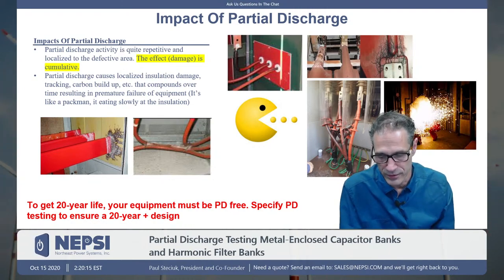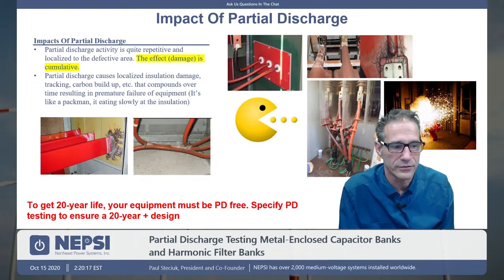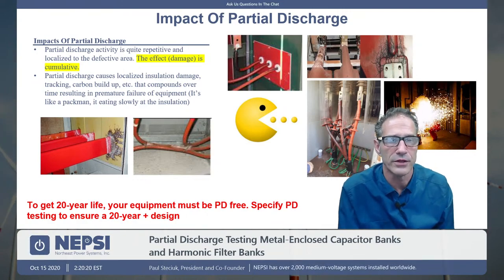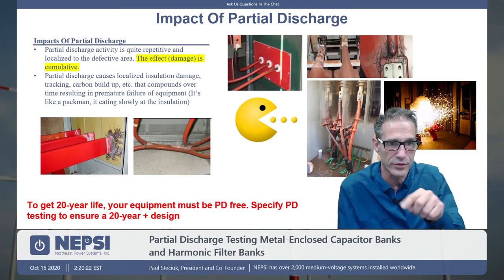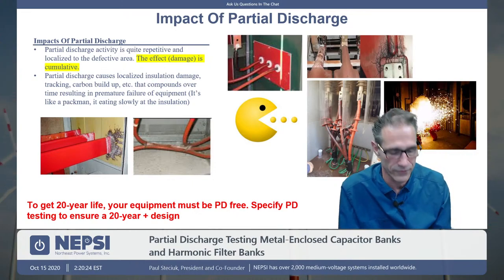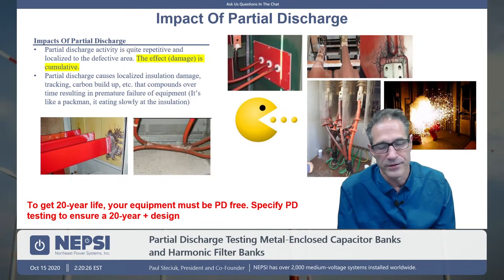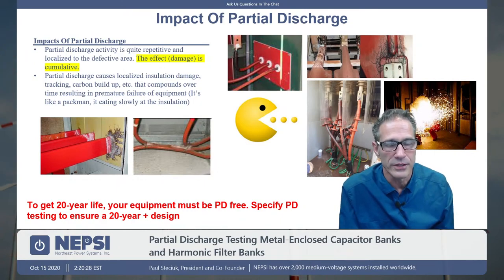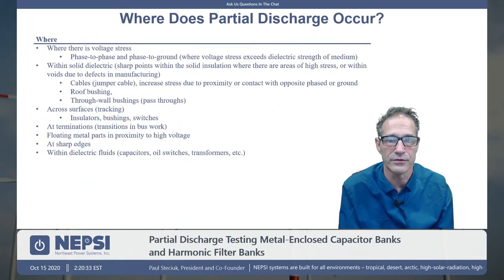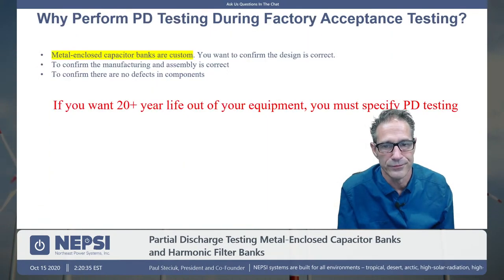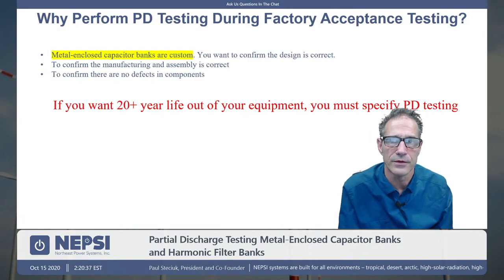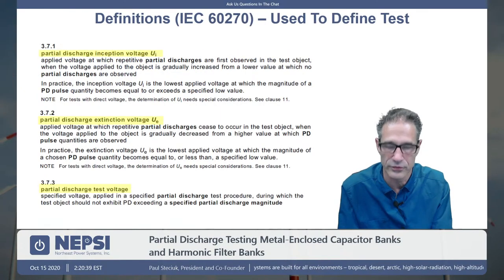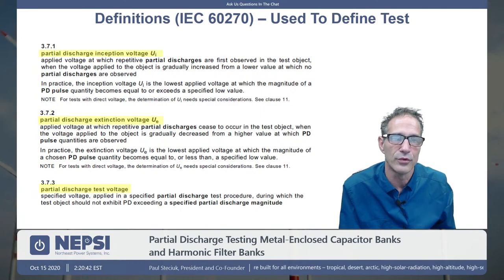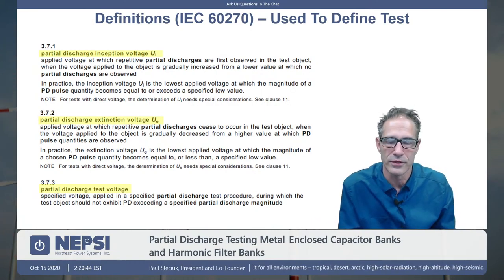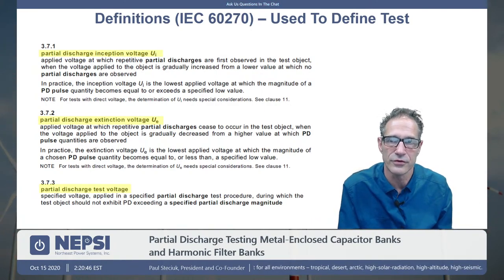I would suggest going to a Raychem termination manual, and I'm sure it's explained there how it's done, and they actually have some pretty good pictures on how it grades that electric field. Incidentally, we do not use medium voltage terminations within our equipment. We stay away from that. There's a good amount of time that goes into putting those terminations on the cables, so we manufacture our equipment without those types of terminations. But the customer, when he comes into our equipment, is using terminations. He has to, according to the electric codes.